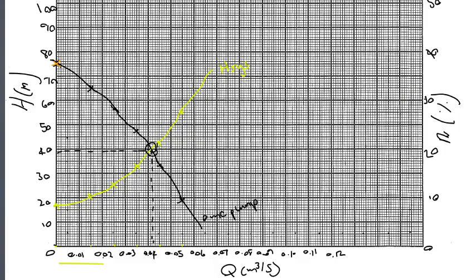So remember, with the pumps in parallel, we multiplied our discharge values by 2. So our Q value here, for our second plot point, will be 0.03. So it will be on this line right here, and at the head value of 65 right here. So this is for your plot for the parallel pumps.